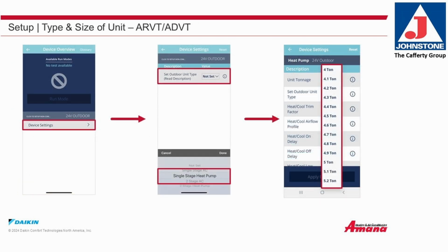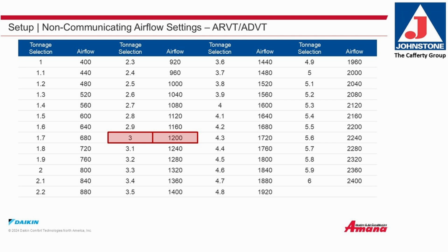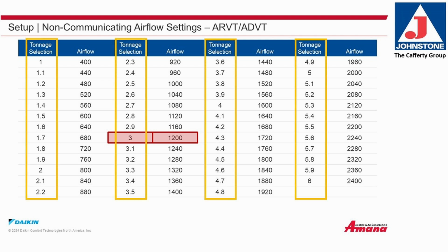On the device overview screen, click on Device Settings. On the device settings screen, Set Outdoor Unit Type will default as Not Set. Choose the appropriate outdoor unit from the list of choices given. In this case, single-stage heat pump. Then you can click Unit Tonnage to select the correct size. Non-communicating airflow settings. In the chart below, you'll see the tonnage selection along with the corresponding airflow.